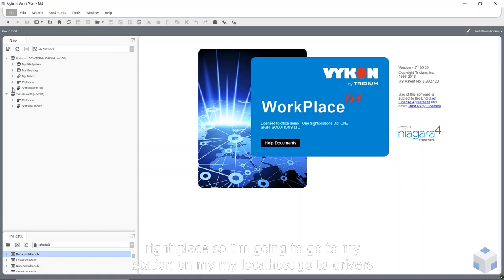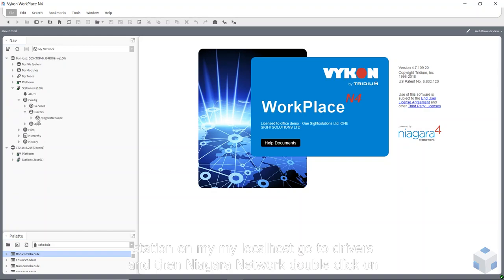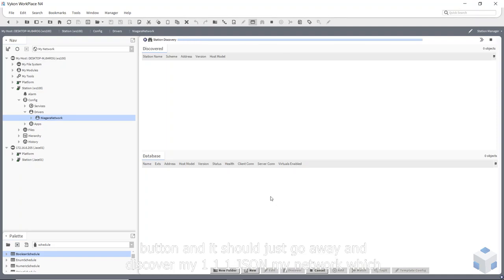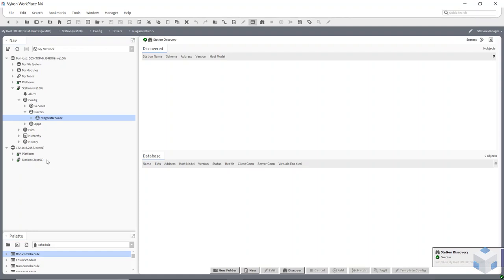So I'm going to go to my station on my local host, go to drivers and then Niagara Network, double click on that. And then I'm going to hit the discover button, and it should just go away and discover my one JACE on my network, which should be this one here, JACE01. Okay, and then I just need to add that to my database.